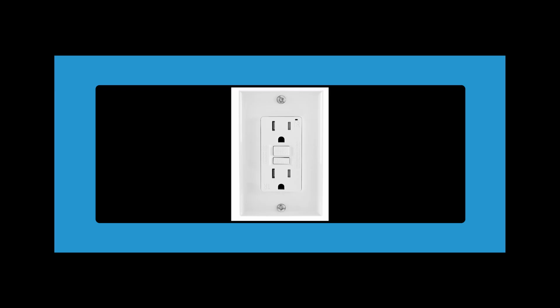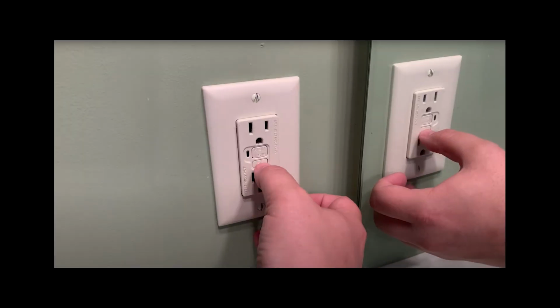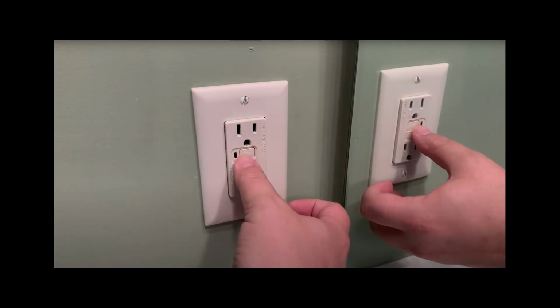So now that we've covered what, where, and why, let's cover the solution. The first step is to try isolating the device that may be causing the nuisance trips. You can do this by unplugging all of the devices from the affected circuit, then resetting the GFCI. If your GFCI resets and you have power, then you know that it's functioning properly and you have a device issue. The next step would be to begin plugging your devices back in one by one to identify which one or what amount is causing the issue. Once you've found the culprit, consider replacing the device if it's outdated, moving it to another circuit if it's a specific device, or reducing the overall load on that circuit by reducing the number of devices.